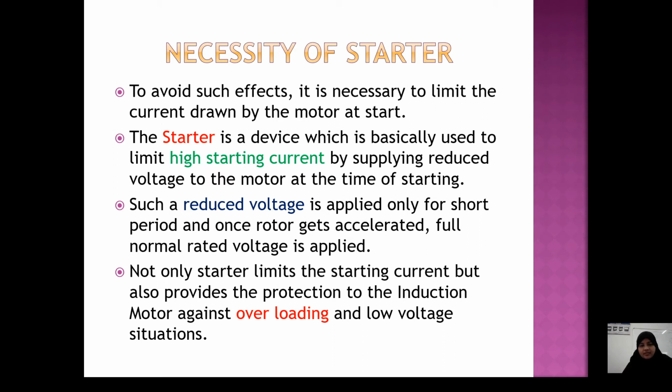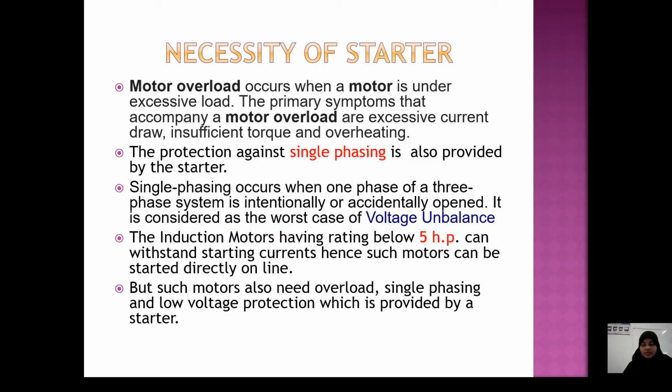Not only does the starter limit the starting current, but it also provides protection to the induction motor against overloading and low voltage situations. So till now we have seen that to reduce the starting current we use a starter, but it also gives protection to the induction motor against overloading and low voltage. Motor overload occurs when the motor is under excessive load. So what are the symptoms? Excessive current drawing, insufficient torque and overheating. These are the primary symptoms that accompany a motor overload.